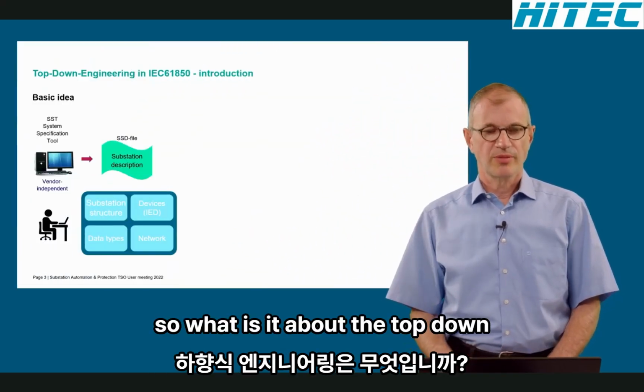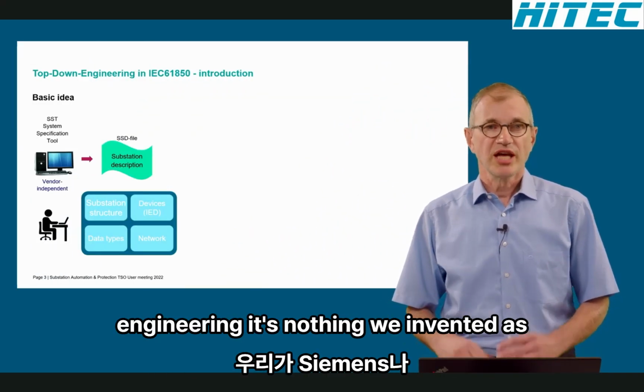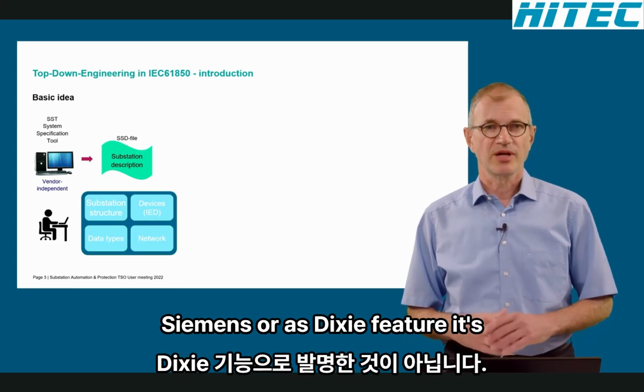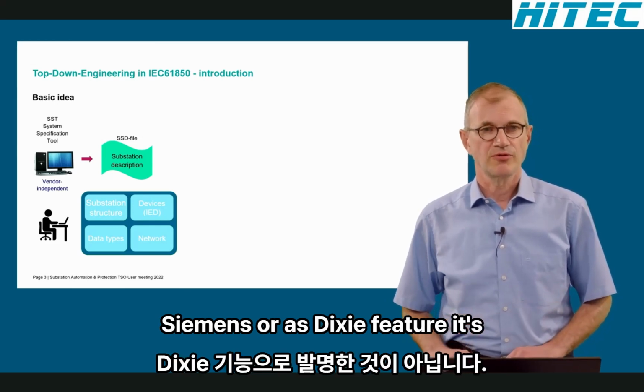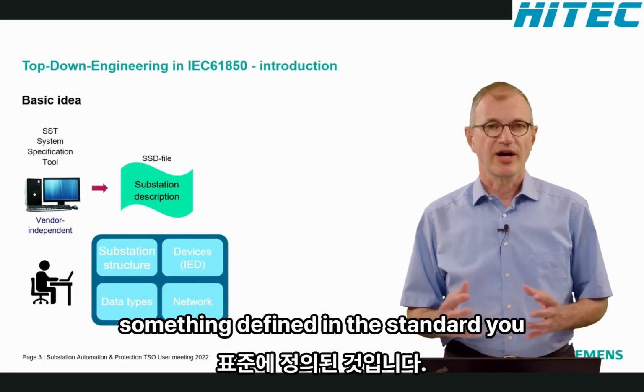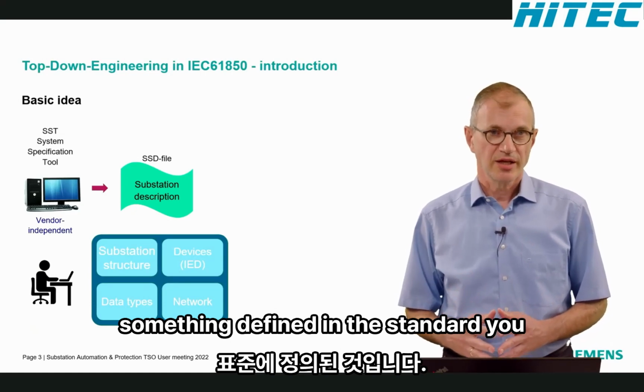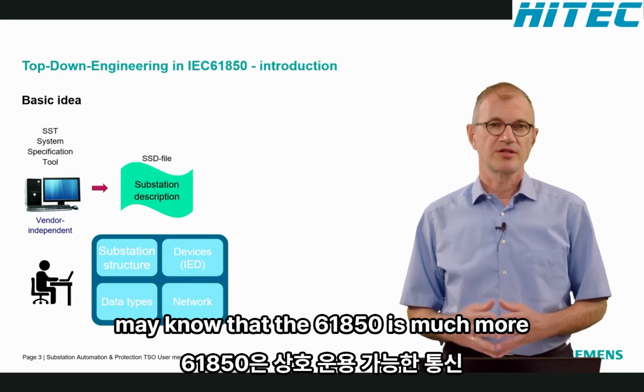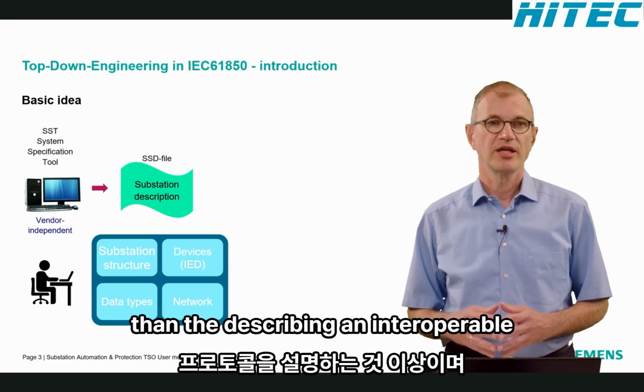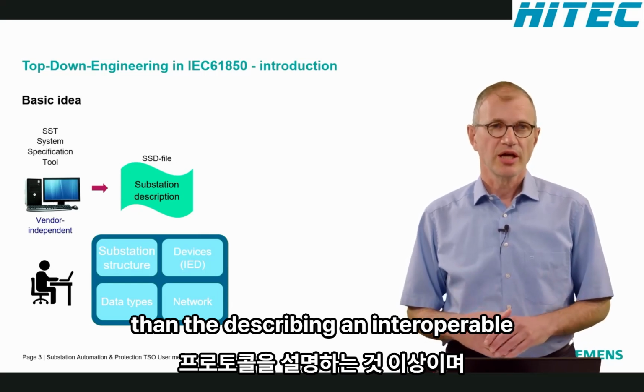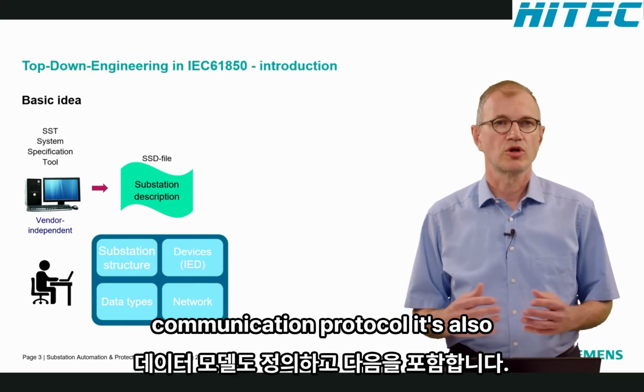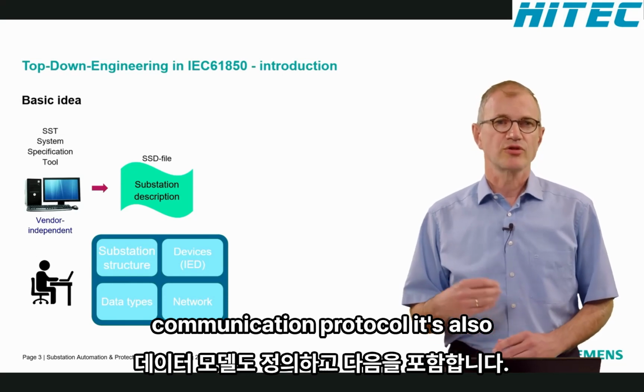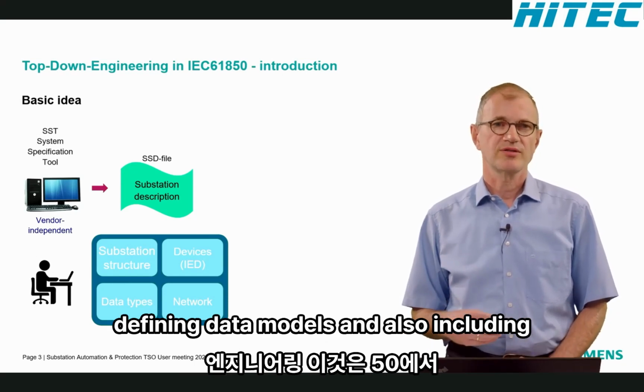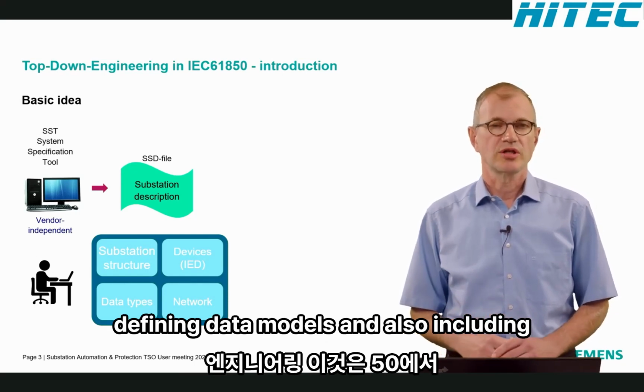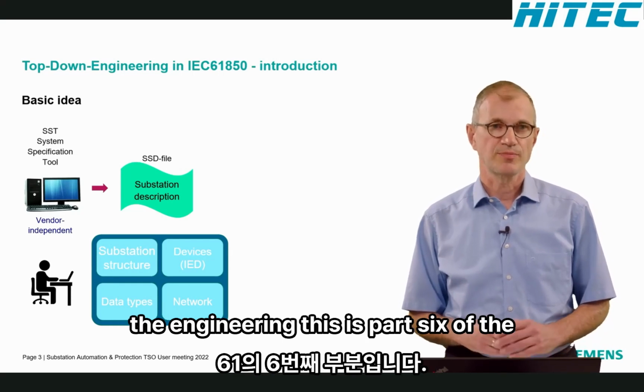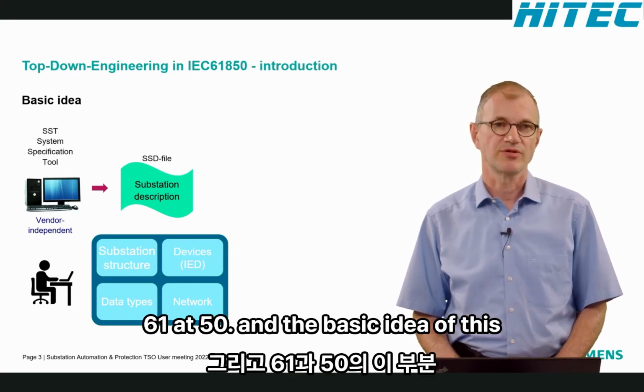So what is it about the top-down engineering? It's nothing we invented as Siemens or as DIGSI feature. It's something defined in the standard. You may know that the 61850 is much more than describing an interoperable communication protocol. It's also defining data models and also including the engineering. This is part 6 of the 61850.